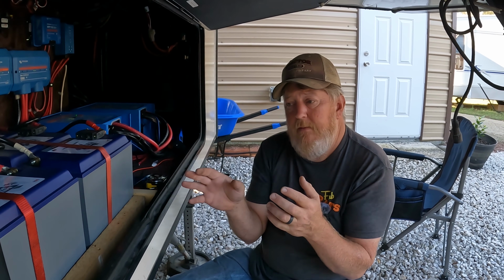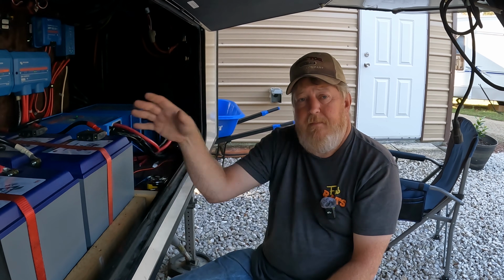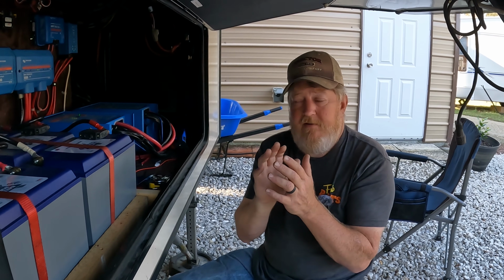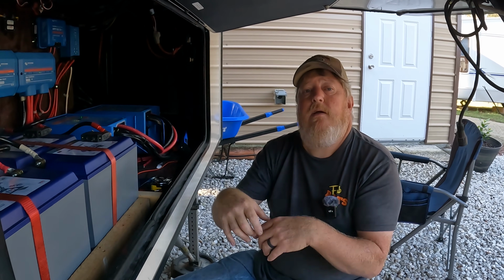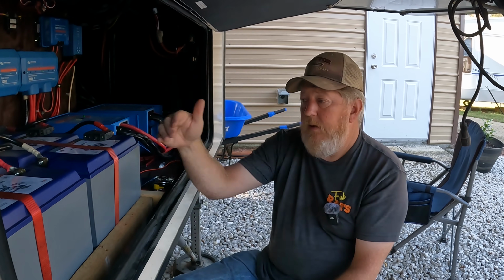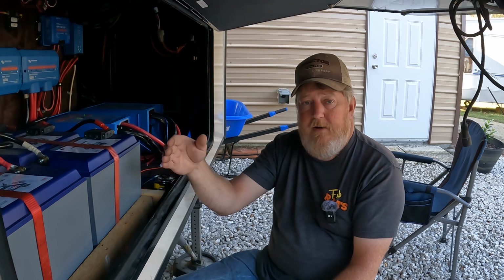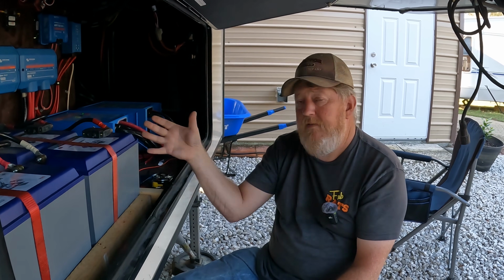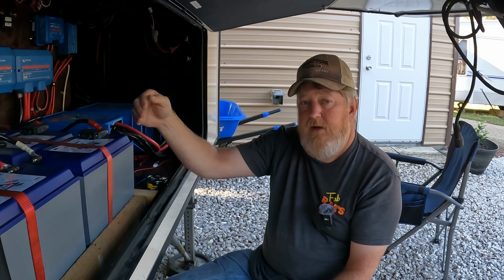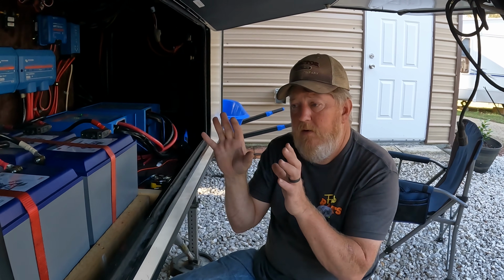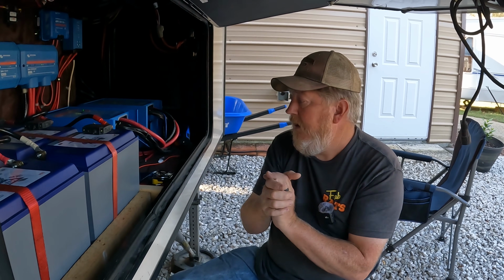They don't even know there's a problem, because the battery will still pass voltage since it's high resistance, and as soon as you load it, the battery fails. We have tested all three of our strings, and all three are actually carrying power. We ran a 50 amp load and tried one string at a time, and it ran just fine, so we know we haven't started that process yet.